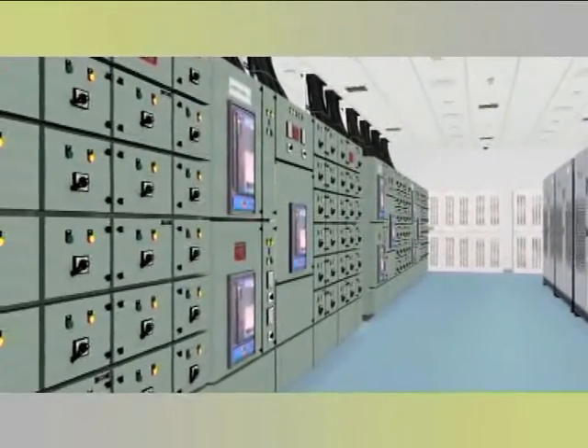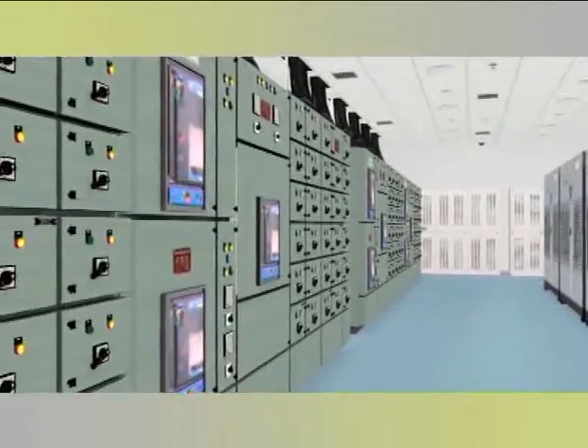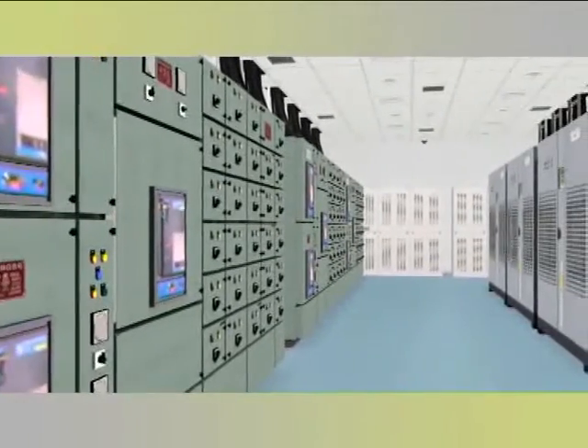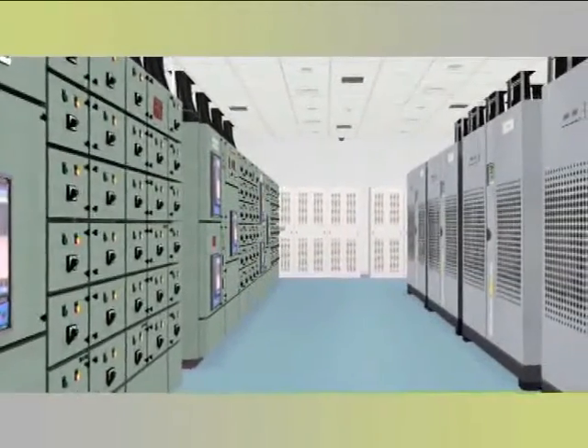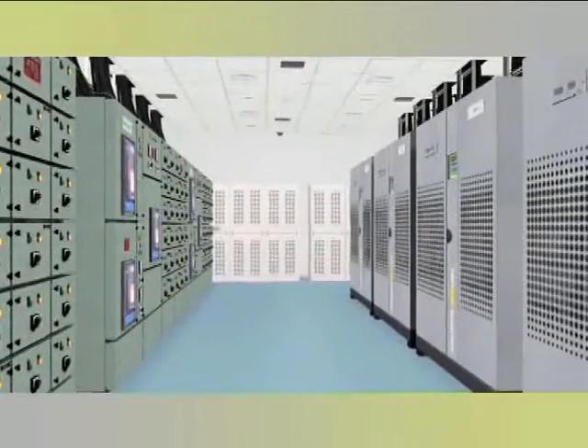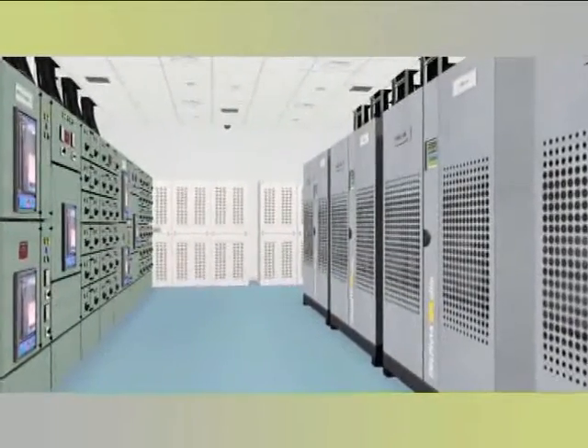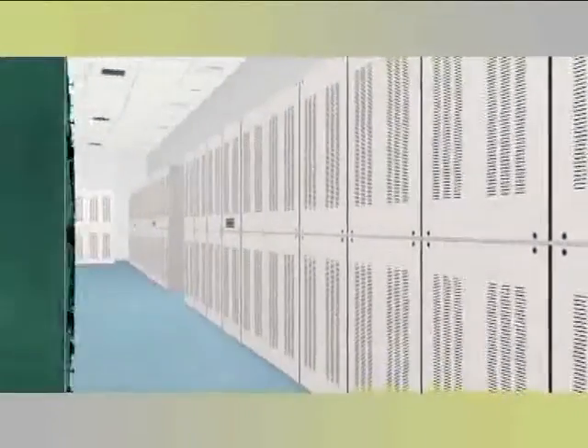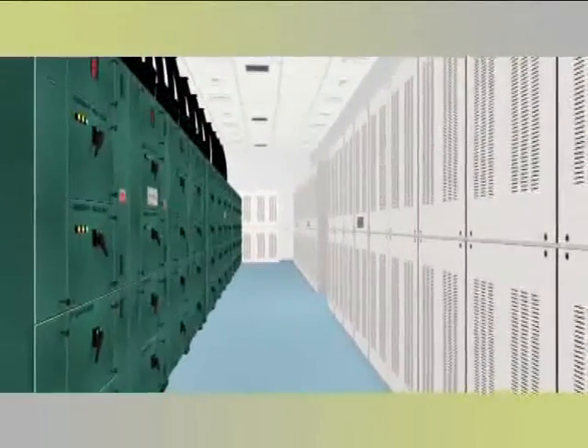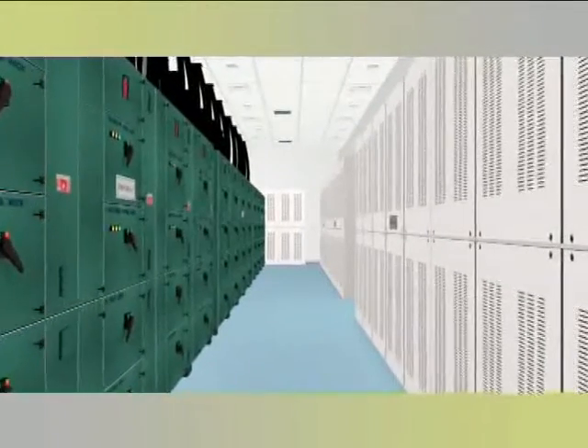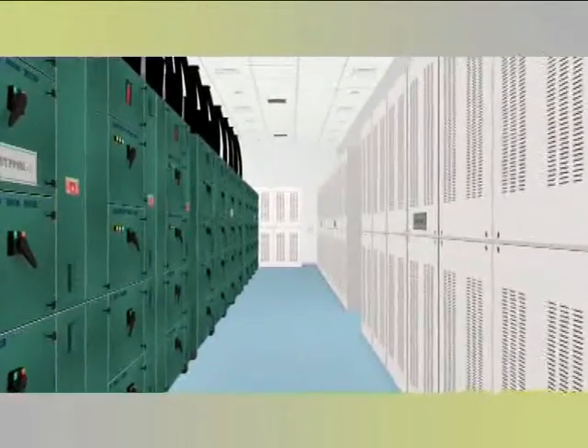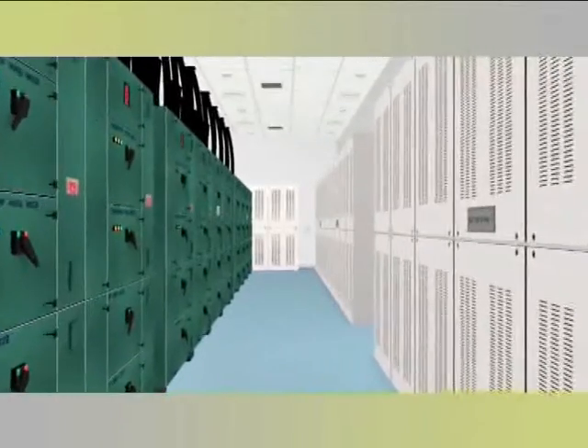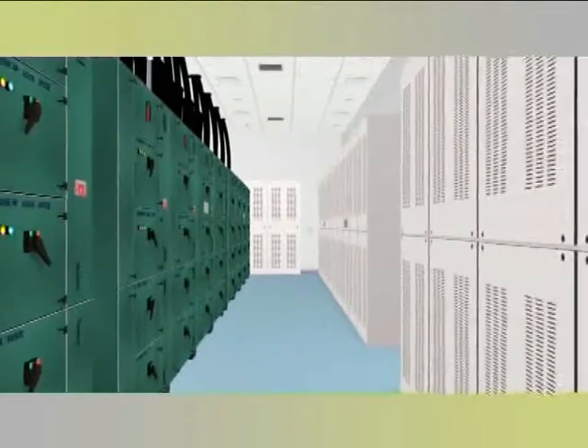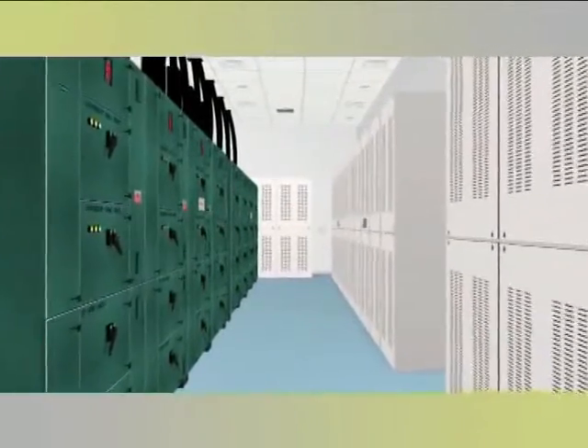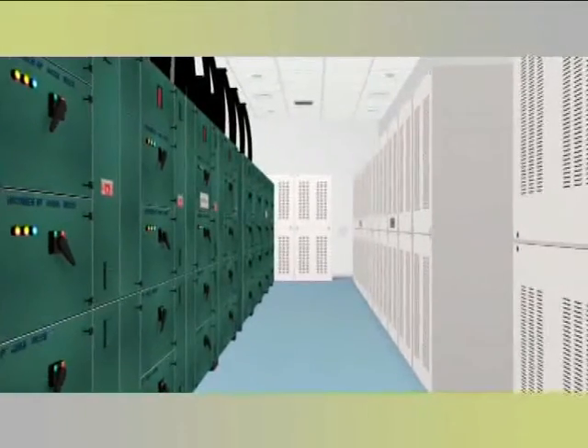The racks in the server halls are connected to the UPS systems through the redundant low-tension or LT panels. And each UPS system is backed up by a separate battery bank. Additionally, primary power is amply backed up with 2 high-power diesel gensets with high-capacity underground fuel tanks, each with a 24-hour supply capacity. The quality of power fed to the racks is constantly monitored through a dedicated branch circuit monitoring system. Thus, the overall power infrastructure at the data center is built in a highly redundant mode to guarantee very high uptimes.